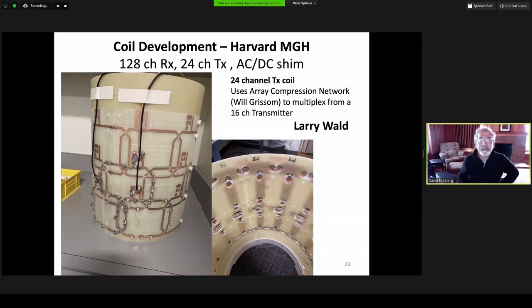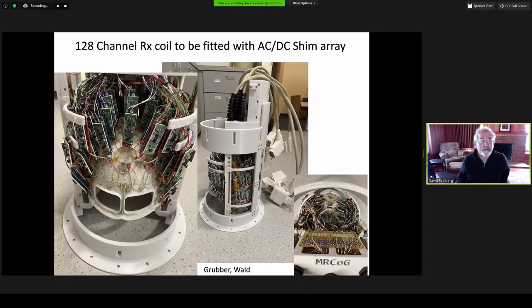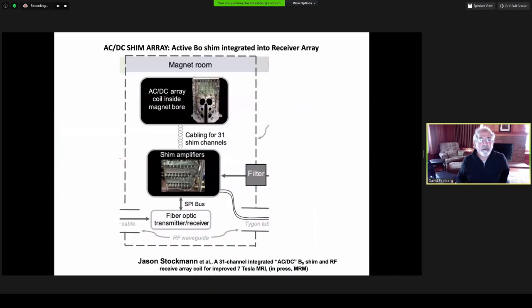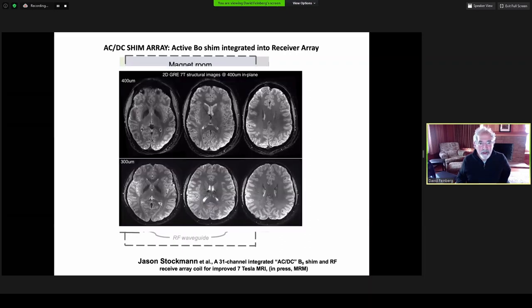The Harvard Group is building a more ambitious 128-channel array, and the transmit system is a 24-channel using an array compression network invented and proposed by Will Grissom that multiplexes the 16-channel transmit. The 128-channel receiver array has already been built and bench-tested, not yet used on the scanner. It will be tested and used for imaging before the AC/DC shim array is integrated into it, which initial testing on 64-channel array at 7T has been performed and gave very good homogeneity and good shimming.